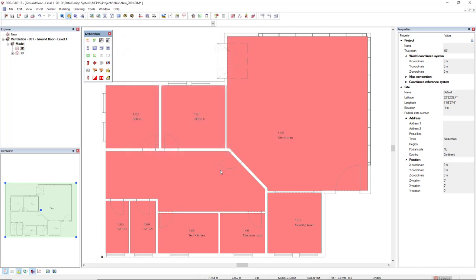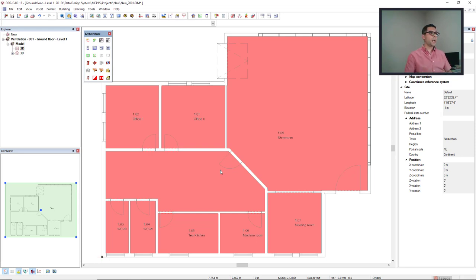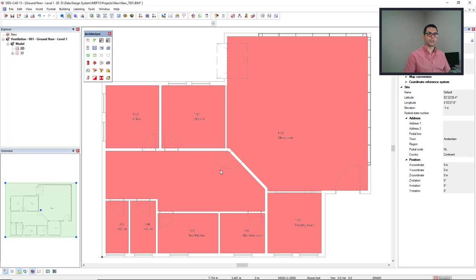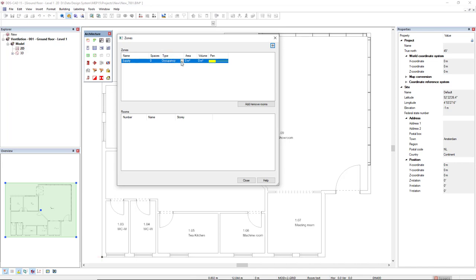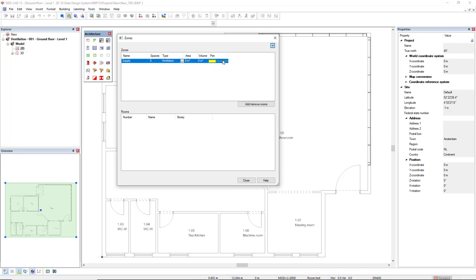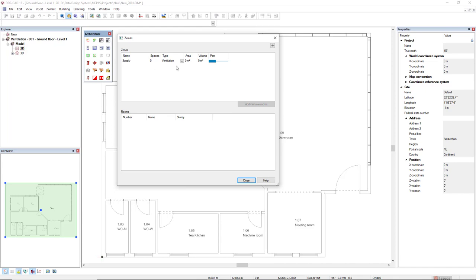Okay. So now let's assume a different workflow because I would like to use this zone for other type of things like to create parts list and sort by zones or for heat load calculation, but not for the airflow requirements anymore. So I need this zone but will not be used for the ventilation discipline. So what I will do, I will come to the function zones and I will create another zone and I will type the name of the zone as supply. And in the column type, instead of occupancy, I will set this to ventilation. And I will change the paint color because it's about supply and we have by default the blue color for supply. So this will be supply and blue.